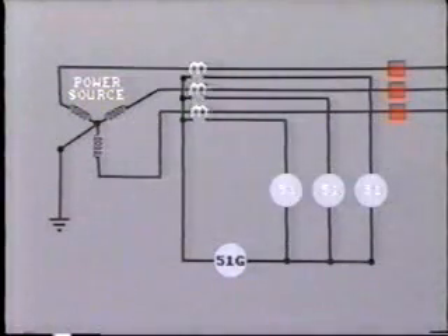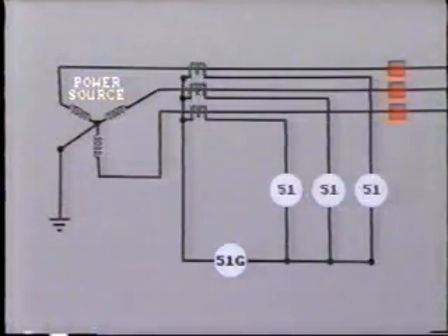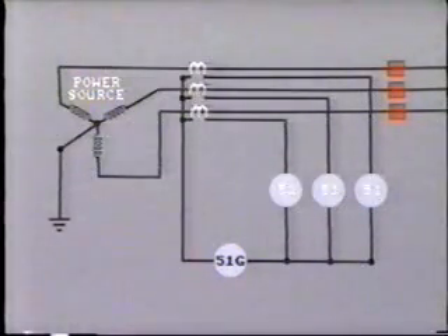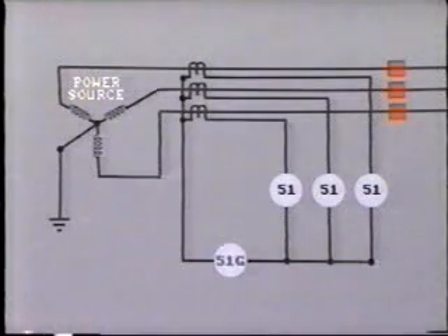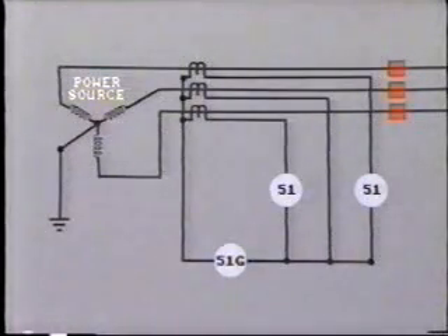Ideally, 3 CTs and 3 overcurrent relays will be installed and connected like this, 1 per phase. An additional relay can be connected to measure any residual current and so detect ground faults. In some installations, one of the phase relays is omitted for economy. This arrangement will still detect phase-to-phase and phase-to-ground faults. However, if a phase relay fails in this setup, there is no backup.